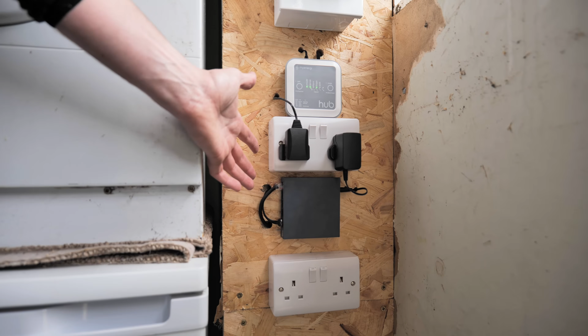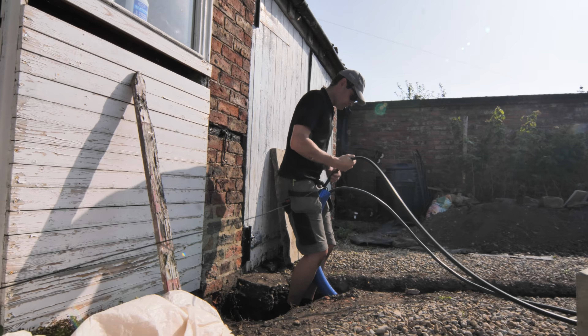So on this job, we've made sure that we've hardwired all of the CT clamps that make this Zappi work. To this building, we've run a Doncaster EV cable with built-in Cat5. A couple of reasons for that: one, it maintains our hardwired CT clamp from the mains, as it's got an inbuilt Cat5 cable, so we can hardwire that grid clamp that is right at the mains protecting that main fuse. That's on one pair of the inbuilt Cat5. On the second pair of the Cat5, if we want to, we can add a solar CT clamp.